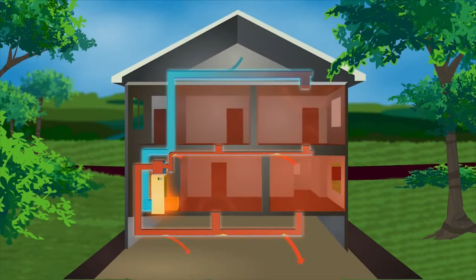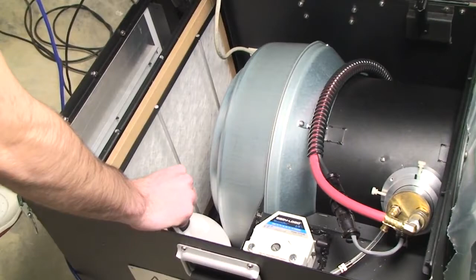When I bought my house, I knew it was a 1980 vintage home and therefore had extremely leaky ducts. I didn't realize they were as leaky as they were. One of the only systems I thought would work for me was an aerosol-based injection system. My duct layout is very complicated and not accessible, so an aerosol injection system was a very good fit for me. And when we did it, we reduced the leakage from over 600 CFM down to about 80. So that's like an 80% reduction in leakage.